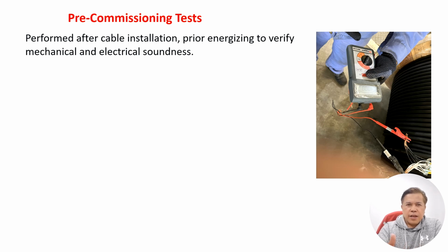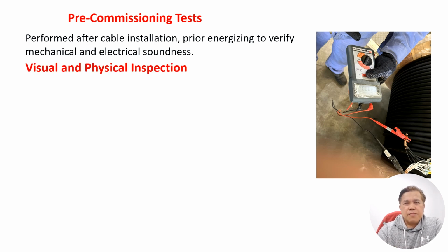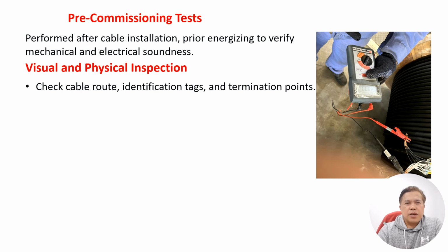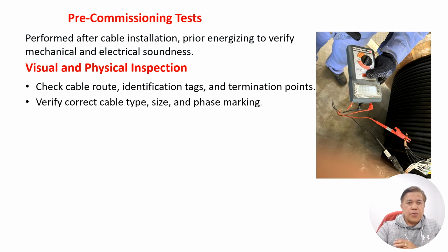electrical damage to the cable strands, outer sheaths, etc. So physical and verification inspections should check the cable route, identification tags, and termination points. That is during the construction phase. All right, so you laid all your cables and provided the tags based on the engineering-approved Issued for Construction drawing. So verify correct cable size and type, and the marking based on that.